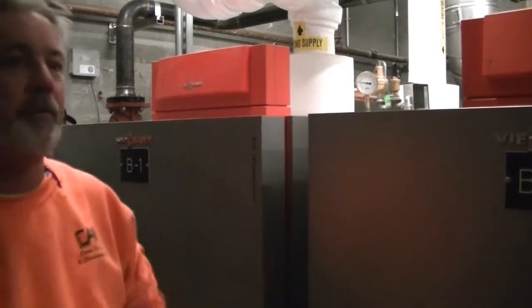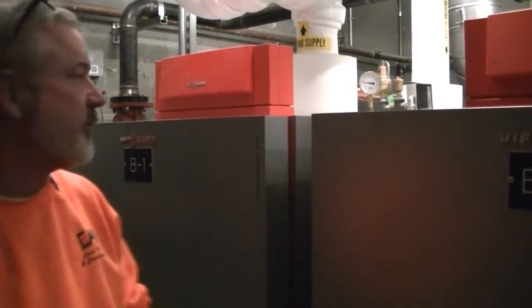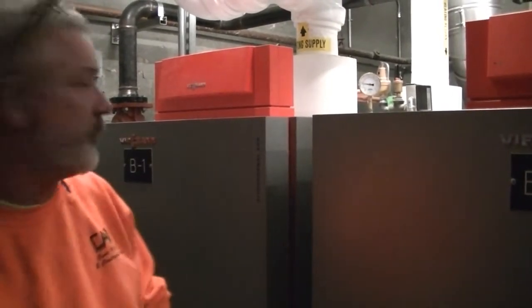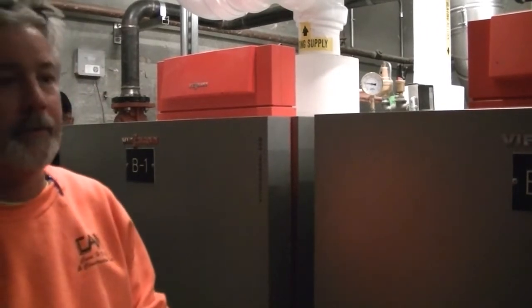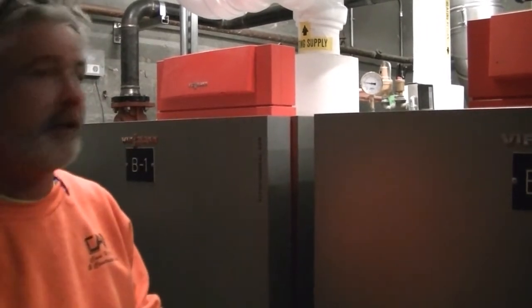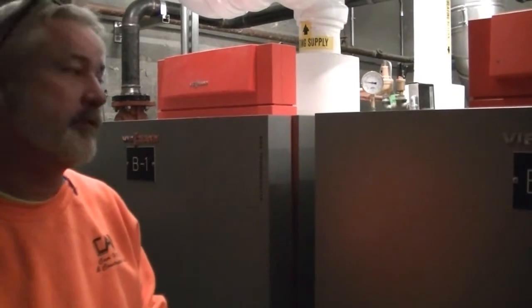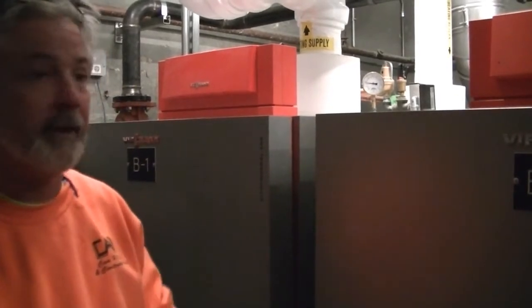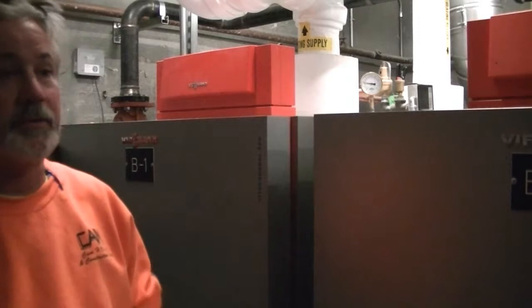the utility company's working. You know how many times I've been called out in the middle of January because there's low gas pressure at the street, and I'm resetting boilers and leaving, coming back the next night, resetting it again, then I put a manometer on it and find out you don't have adequate gas pressure, okay?